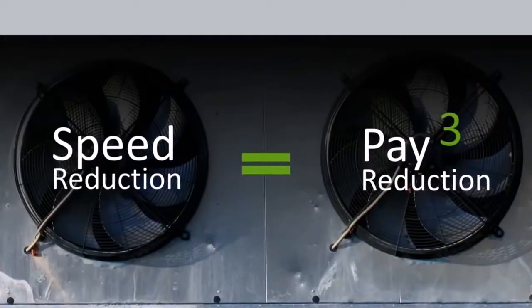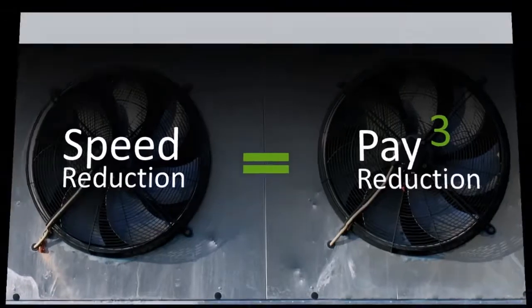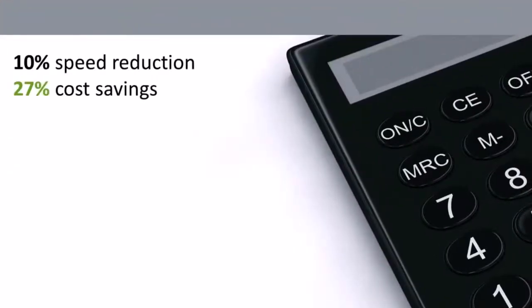The basic concept with the savings for VFDs is that your speed and your flow are more or less proportional, but the energy consumption is cubed. If you're running your motor at full speed, or 60 Hertz, you don't have any savings, but any reduction pays the reduction cubed. But let's say you're able to take that oversized motor down to 90%. So at 90%, you're at 54 Hertz, or a 10% slowdown output from the VFD. Your savings is 27%. How's that?